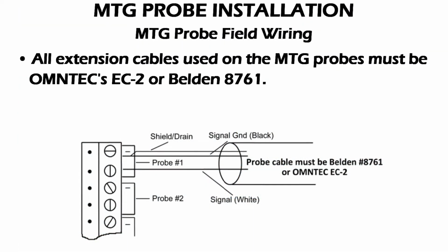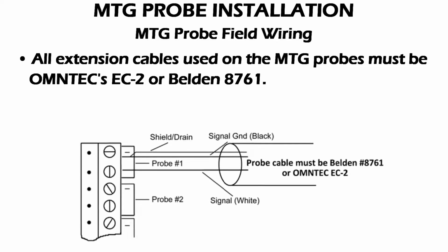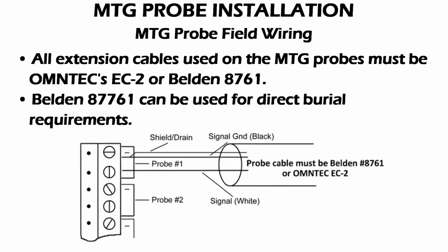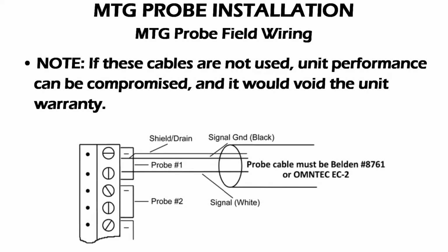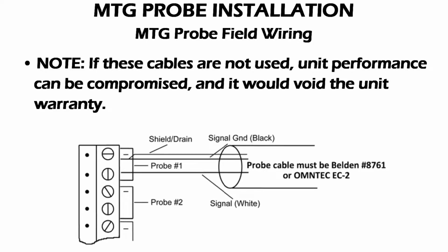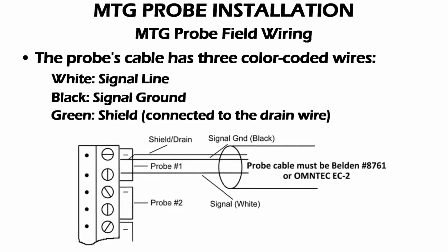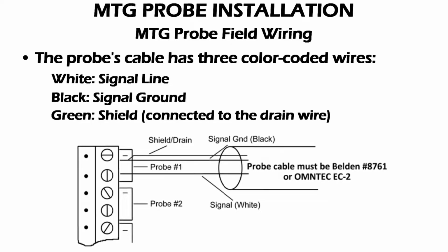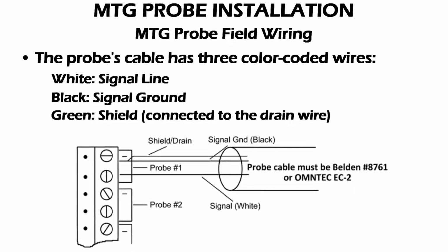All extension cables used on the MTG probes must be OMNTEC EC2 or the Belden 8761. The Belden 8761 can be used for direct burial requirements. It is important to note that, if these cables are not used, unit performance can be compromised, and it would void unit warranty. The probe cable has 3 color-coded wires. White, which is the signal line. Black, which is the signal ground, and green, which is the shield. This connects to the extension cable's drain wire.